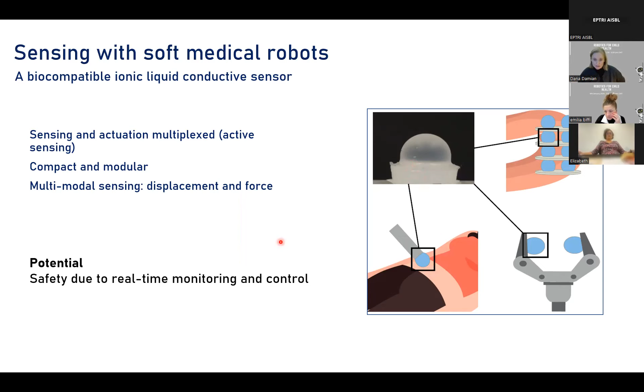This type of sensor can be applied to a variety of medical applications. It could be a catheter, if you will, but it also can be used at the tip of a probe, or of course, in the case of our robotic implants. So the work principle is shown in this slide. The building block is a membrane that inflates, in which we pressurize this ionic conductive liquid. And by reading the resistance of this conductive liquid, we can get a change in resistance that speaks about the displacement of this inflating balloon, of the force that is applied on the environment, such as the tissue.